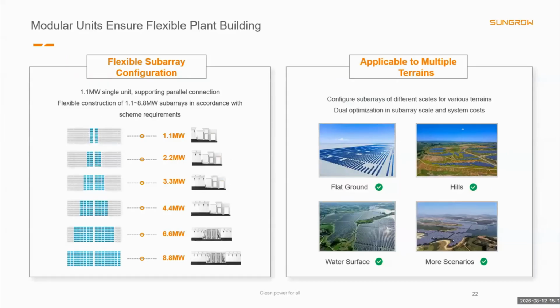So each 1.1 megawatt unit can be combined to form different subarray sizes. This gives EPCs or owners greater flexibility on hills, irregular land, or water surfaces. Instead of forcing the site into one fixed block size, the electrical design can follow the terrain. This helps optimize land use and system cost.